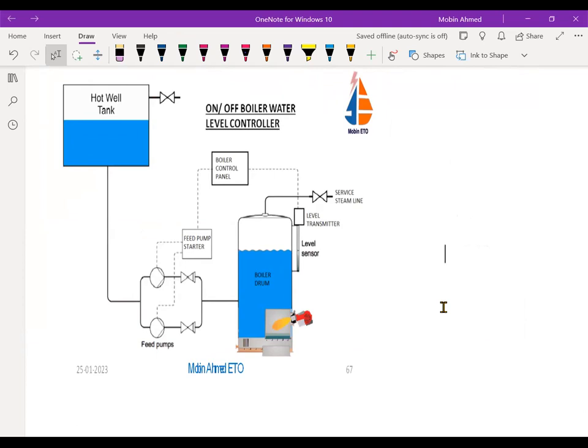This is a very simple one. So we are going to have a level transmitter, and generally the level transmitter we use gives a discrete signal. Discrete means an on and off signal. That is the level sensor we are going to put here. So it is going to give either a start signal or a stop signal. So this is a pump stop and start signal. This is known as a discrete signal.